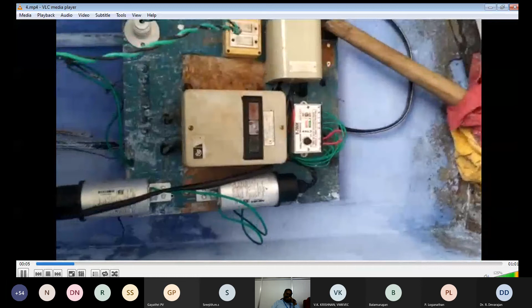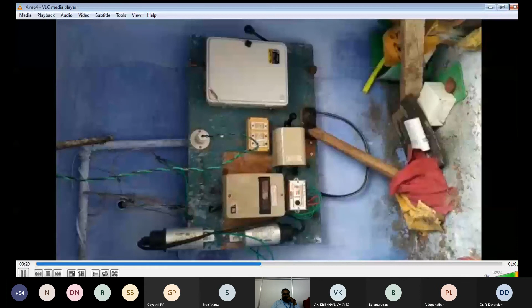This is on agriculture services, where we provided the shunt capacitor, multiple capacitors, to improve the low power factor to a unity power factor. This costs around 600 or 700 rupees, and the utility itself installed it at the consumer premises to improve the voltage profile, to reduce the line current, and to improve the power factor. They install this shunt capacitor.